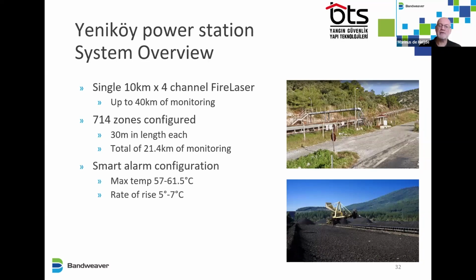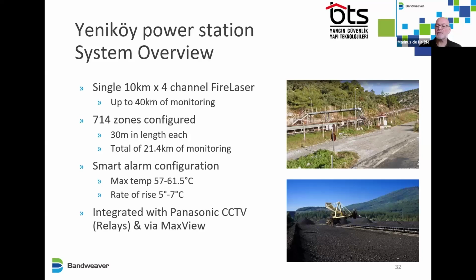We set 2 of the alarms. For the maximum temperature, we set in different zones from 57 to 61.5 Celsius. The rate of rise, we set at quite a low range here, 5 to 7 degrees. And we integrated with a Panasonic CCTV monitoring station via the relays, but we also used our in-house MaxView. So there's a few slides on it, but it is really a different type of product, which we market next to our linear heat detection.